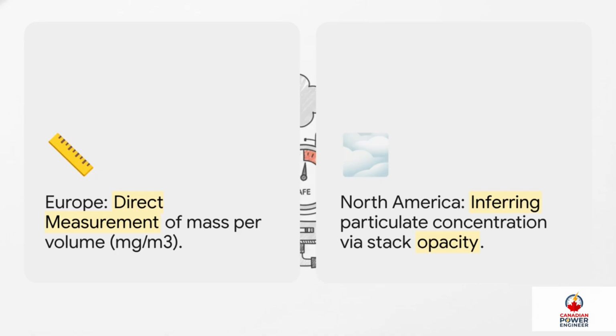So, in North America, the standard practice is quite different. Because the technology to continuously and directly measure particulate mass is so challenging, North America relies on inferring that concentration by measuring something else entirely: stack opacity.